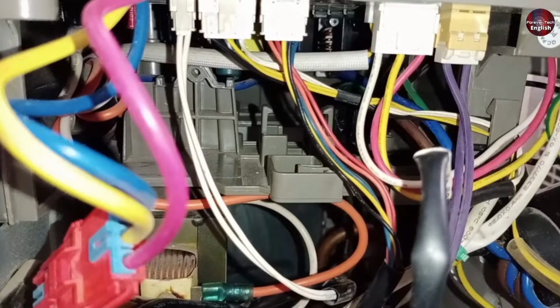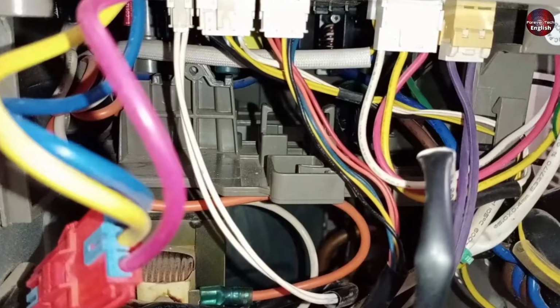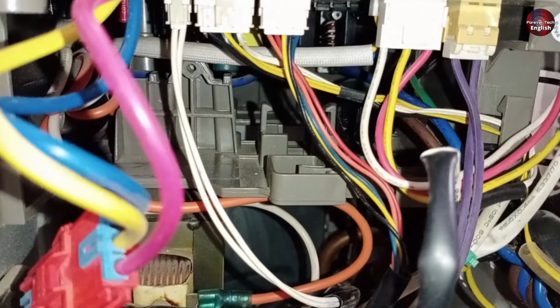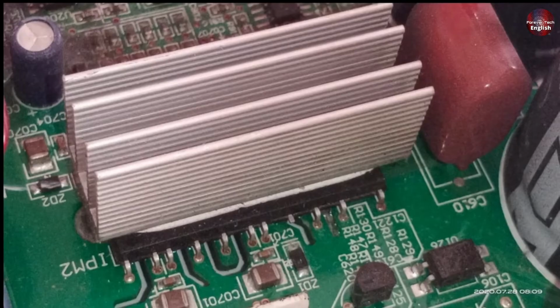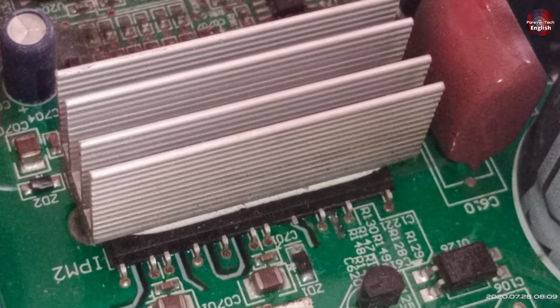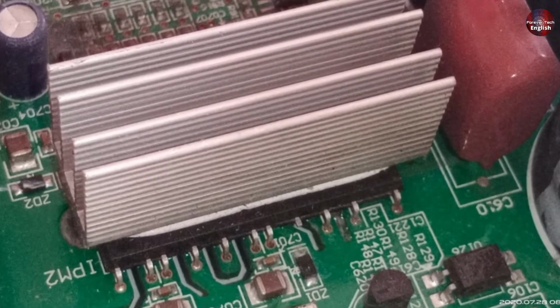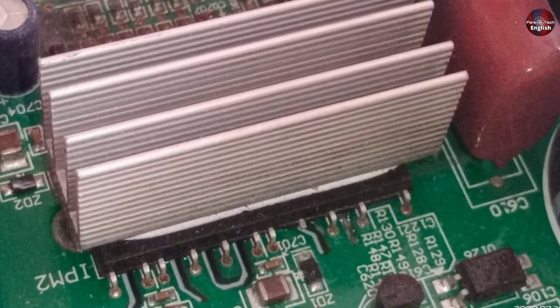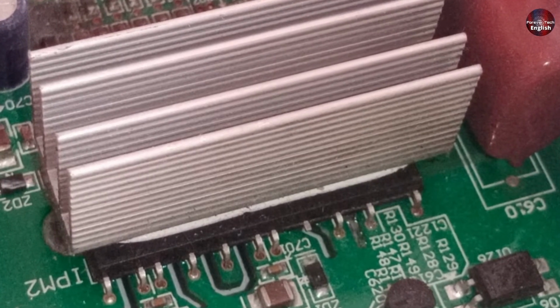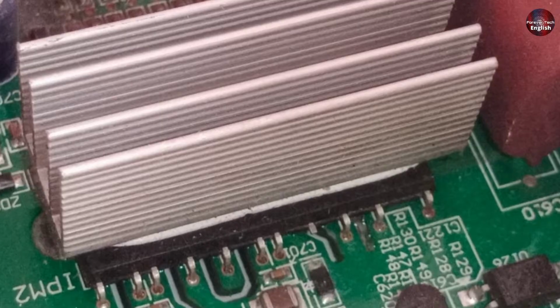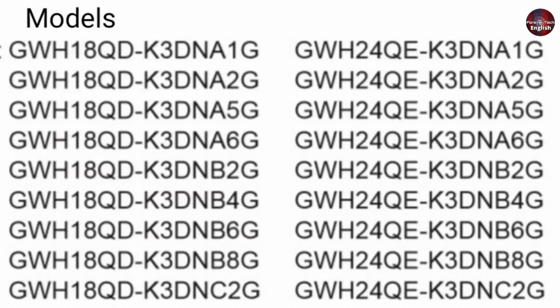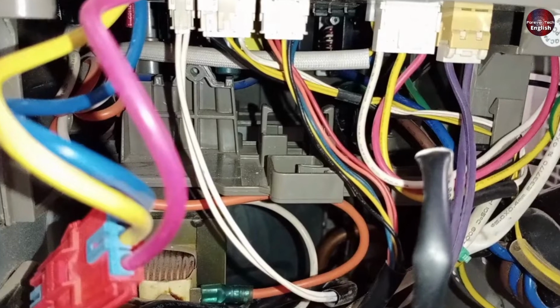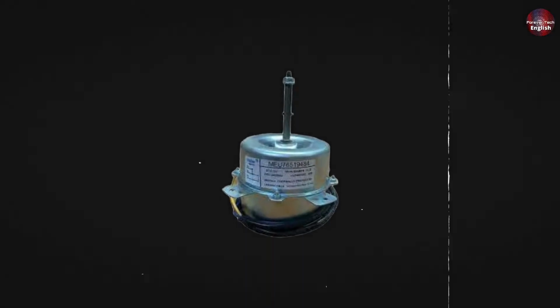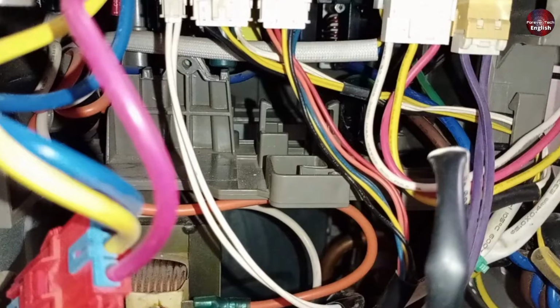Sometimes, due to the unit's vibration, some connectors become loose, causing them to lose contact with each other. Additionally, the outdoor unit has an IPM, Intelligent Power Module, installed for the DC fan motor. If that gets damaged, the indoor unit will also display the L3 error code. I'd also like to give you more information. Some models have the L3 error code for units with DC motors, while in other models that don't have the L3 error, they use an AC fan motor. This is also something to keep in mind.